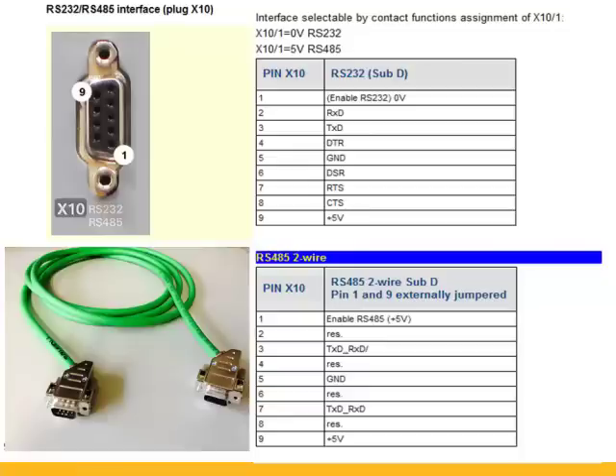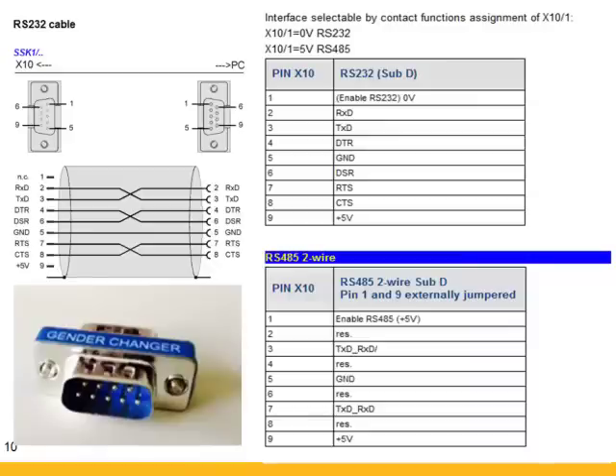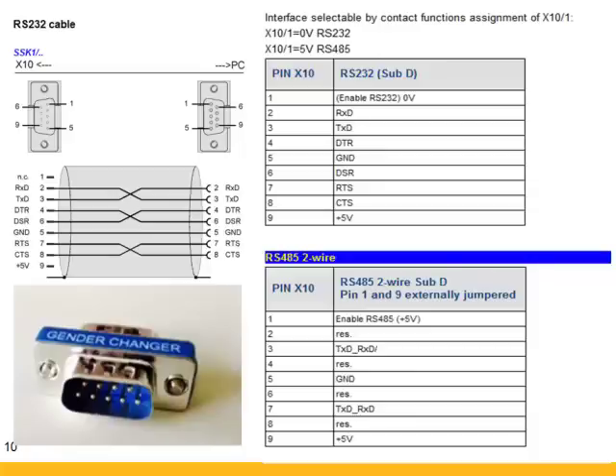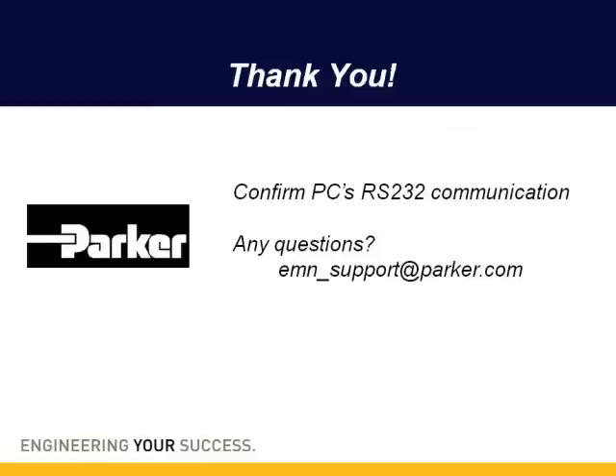If you're using a straight through cable and a gender changer, the straight through cables typically do have that pin populated and the gender changer will pass that through. And commonly on power up the drive will come up in 485 mode. So the easiest way to do that is take a pair of wire snips and actually snip that pin out either on the gender changer or on the cable itself. And then cycle power on the 24 volts on the Compax 3 for it to wake up in 232 mode. So that is how you quickly confirm the PC's RS-232 communication is working.